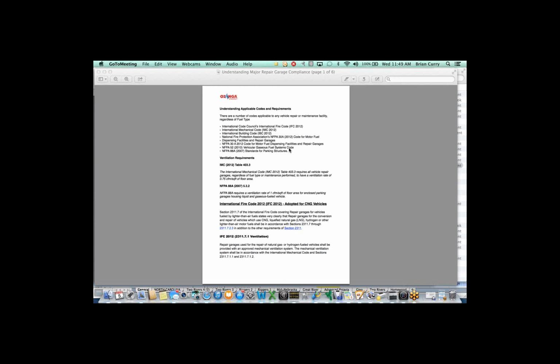So the simple requirement of being in compliance with standard International Mechanical Code and IFC codes, to be compliant when working on a CNG vehicle in a major repair shop, would be continuous ventilation. Well, anybody working in a northern extreme like Chicago or Wisconsin is not going to want to turn the exhaust fans on and leave them running continuously. So we sidestep that requirement. What we do is purchase a methane detection system for each facility. The methane detection systems that we install are typically all infrared. We size the kit or the system for the shop.